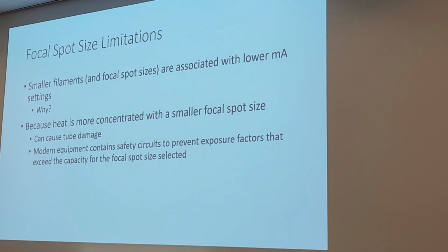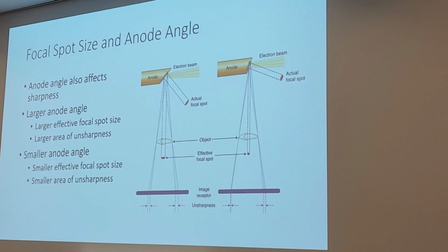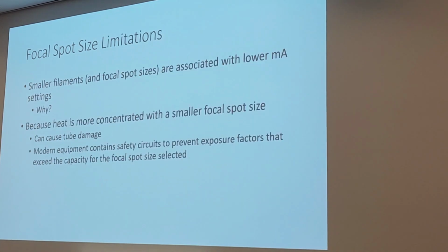So yes, too bad. I'm sorry. Small gives you a small focal spot. If you have a small focal spot, you cannot use a high mA.